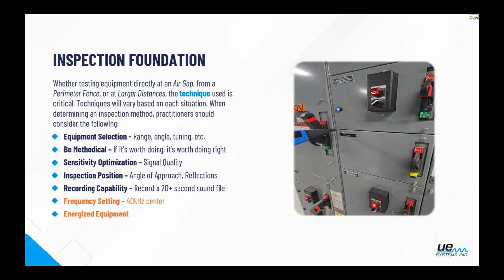The other point that is always critical to keep in mind is very similar to infrared. What is the angle that you're inspecting from? In the same context, if you were inspecting an asset outside at a sharp angle, you could get a lot of reflected heat showing off of that. Solar load, same thing with sound. Sound, especially ultrasound, loves to reflect off of surfaces. So we generally try to make a head-on approach to whatever we're inspecting. If it's something that has a lot of curved surfaces, or other pieces of equipment around it, those are things that we have to be mindful of and possibly change the angle that we're inspecting from. So just always be aware of reflected surfaces.